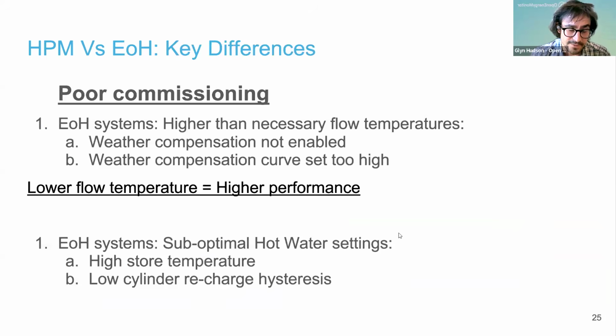So the key difference we've seen between the systems on HeatPumpMonitor and the electrification of heat systems, which is the main differentiating factor, was poor commissioning. Matt touched on this. Basically, the electrification of heat systems, almost all of them were running much higher than necessary flow temperatures. So the golden rule with heat pumps is the lower the flow temperature, the higher the performance. That's just physics. So that's something we saw again and again when we were analysing the electrification of heat data.